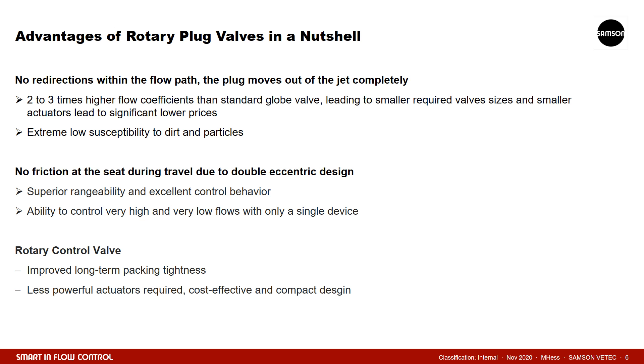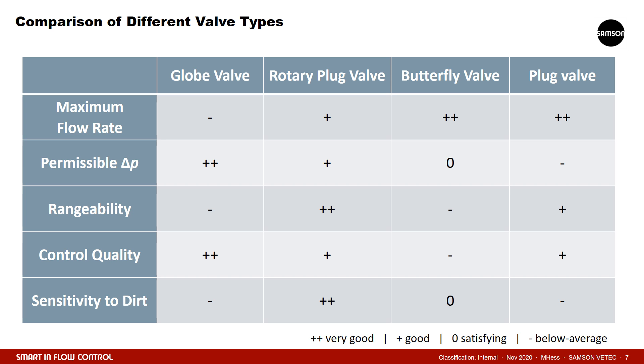Finally, the rotating motion causes less wear and tear on the packing, leading to improved long-term tightness. As the plug doesn't have to close against the full pressure like in a globe valve, but simply turns away, the necessary actuators are less powerful, more cost effective, and have a more compact design compared to actuators for sliding stem valves.